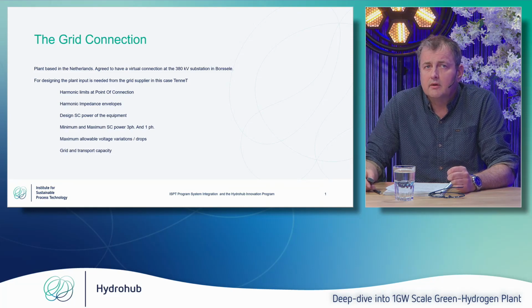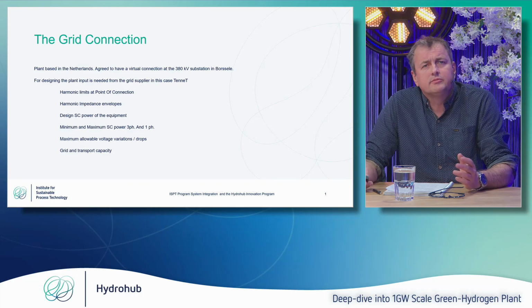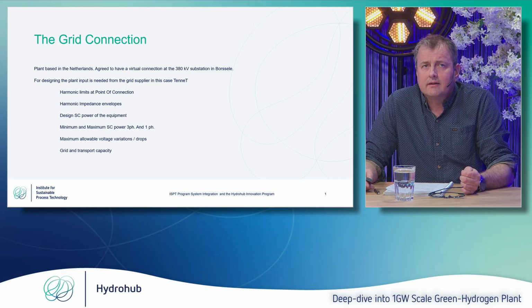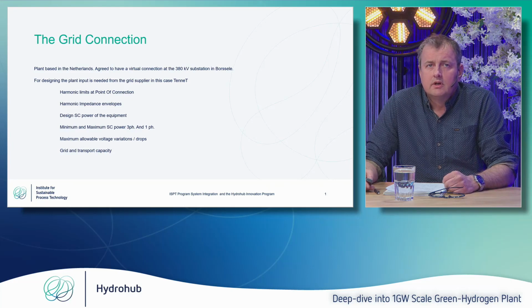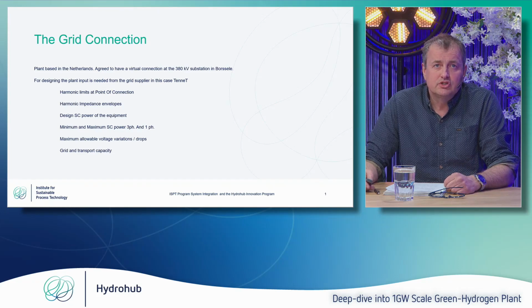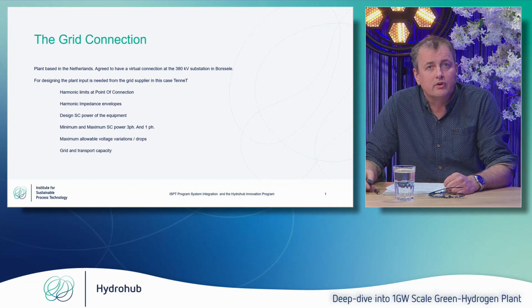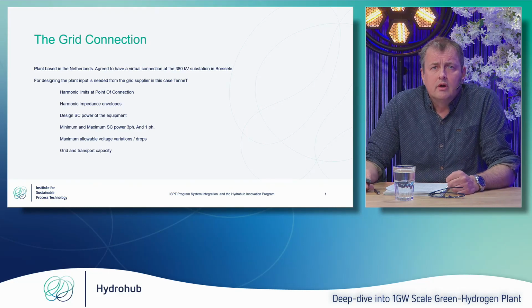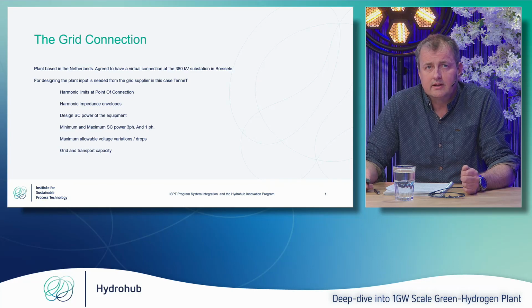One of the things was the harmonic limits at the point of connection. If you would have asked me this 20 years ago, the harmonic limits were not the first point to think about, due to the fact that 20, 30 years ago, the number of semiconductors or non-linear loads was much less than nowadays. And definitely for such a plant where we need a lot of rectifiers, the harmonic limits are very important. If you look at the harmonic limits at the point of connection, TenneT gave us some restrictions with respect to those limits.